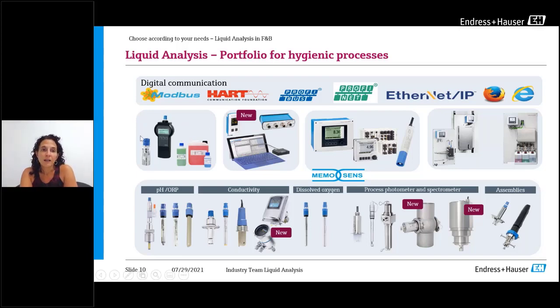And here what we have are the things that we use for commissioning, maintenance, or calibration. For example, the buffers that we use to calibrate the pH sensors. On the right side, you will see the solutions that are specifically developed for the food and beverage industry, like this one, that takes the pH sensor out of the process, cleans the pH sensor, and then calibrates the pH sensor, and then puts it back again. So it's for very high precision, and also to have independence of the maintenance in this measuring point.